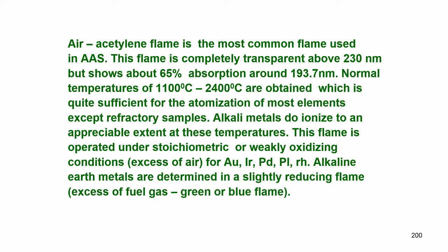Normal temperatures of about 2400 degrees are obtained using the air acetylene flame, depending upon the flow rate of the gas and oxidizer. This is quite sufficient for the atomization of most elements except refractory elements. Alkali metals, sodium, cesium, potassium, etc., do ionize to an appreciable extent if I put them in the air acetylene flame.